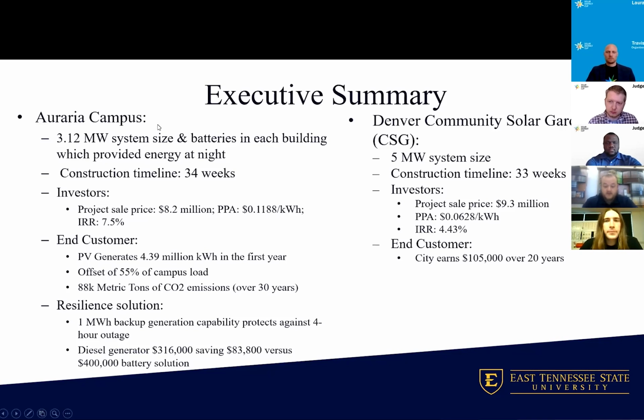The resiliency solution for the science building involved using a 1.02 megawatt hour backup generator costing $316,000, saving $83,800 versus a $400,000 battery solution, to cover 100% resiliency against a 4-hour outage.